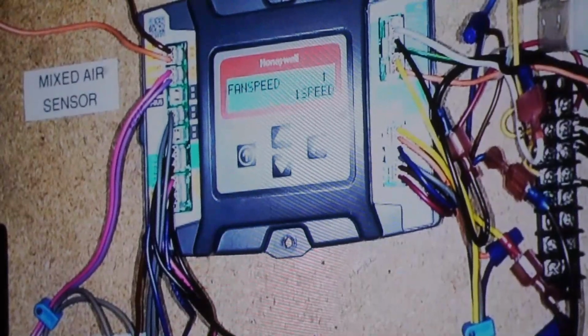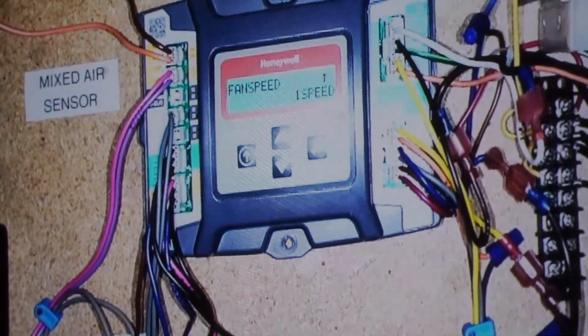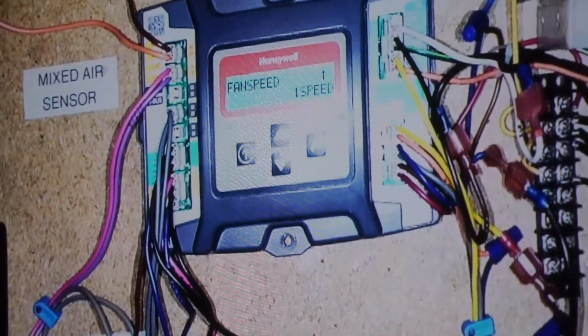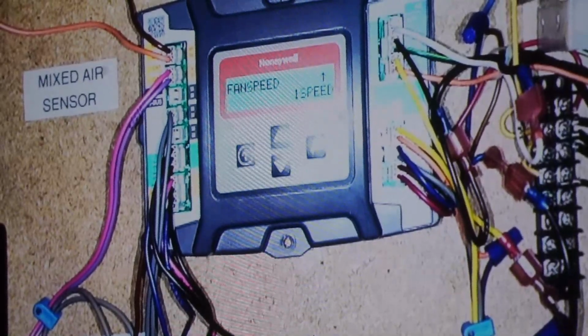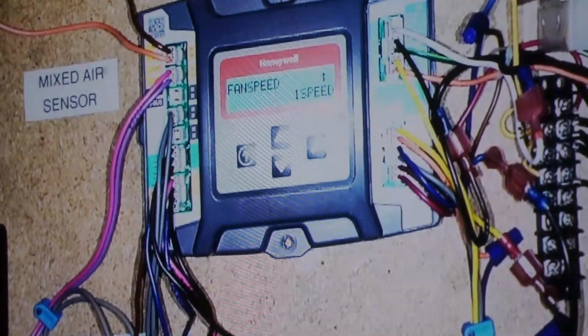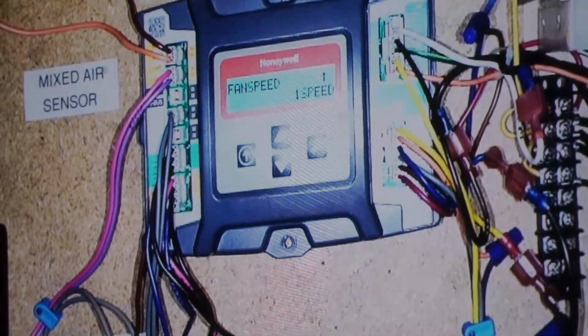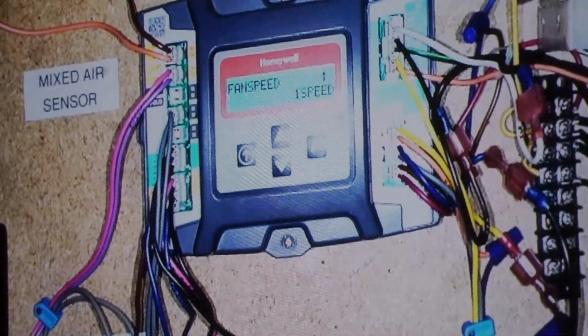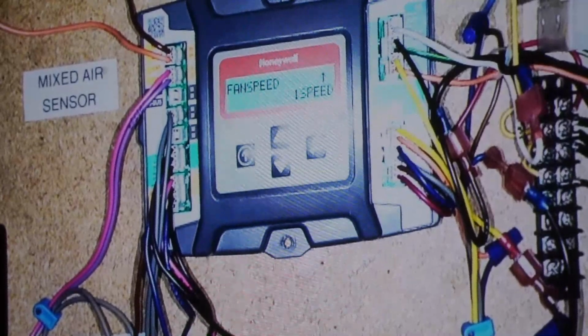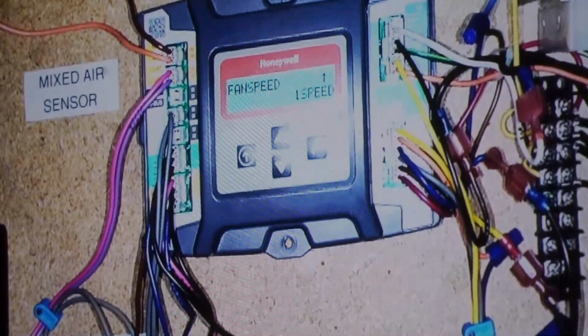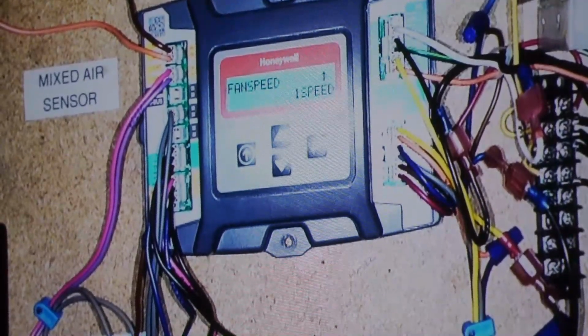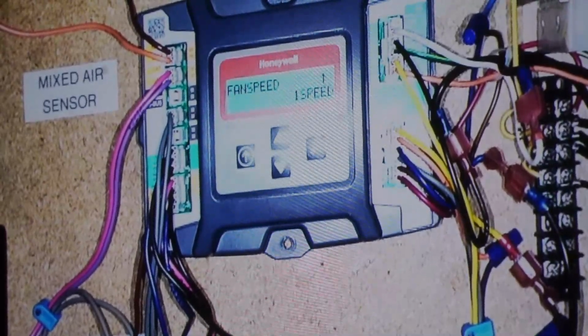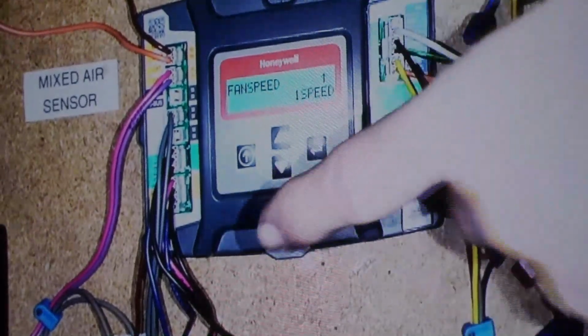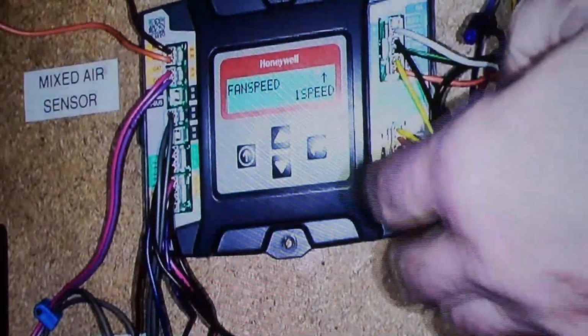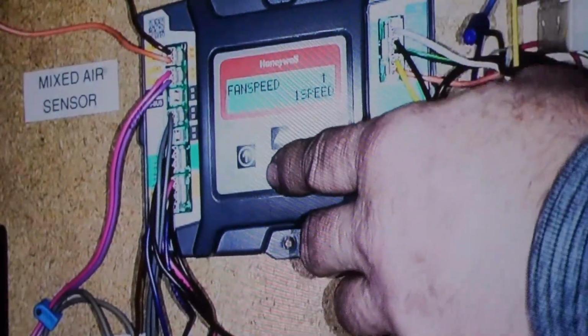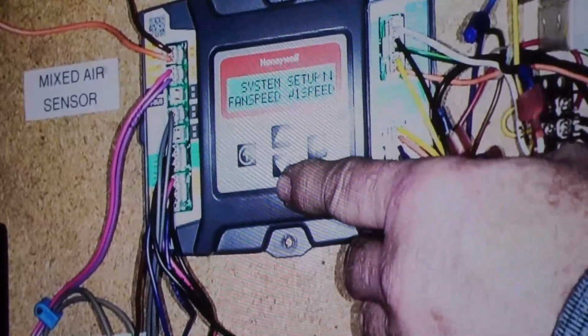Remember the mix box, the amount of outside air we bring in is based on the negative pressure in that mix box. Remember we saw that picture with the different colors on it? What's going to happen to the negative pressure when we go to low fan speed? It's going to reduce. So we need to open that outside air damper more to get the same CFM. So if we get a Y1 call on a staged air volume unit, we need to have a higher outside air damper position. Same CFM. Yes, sir. And that's the end of that menu.